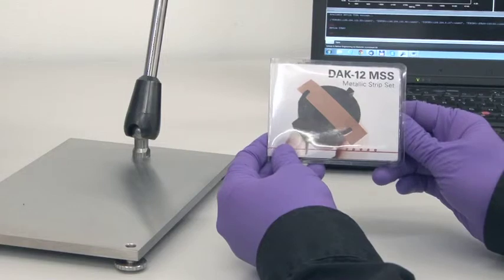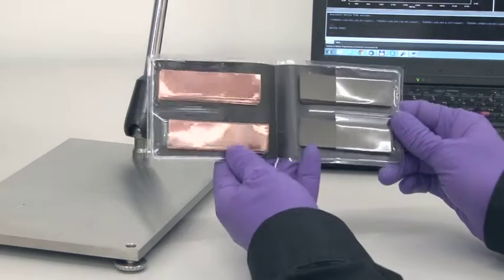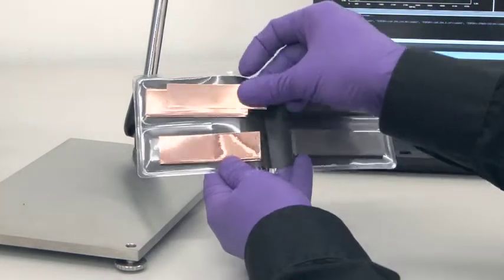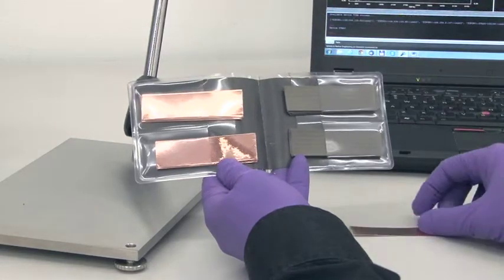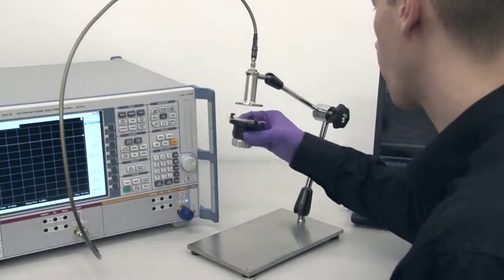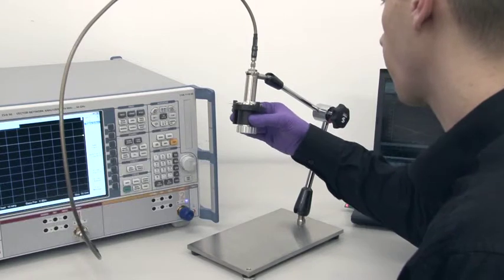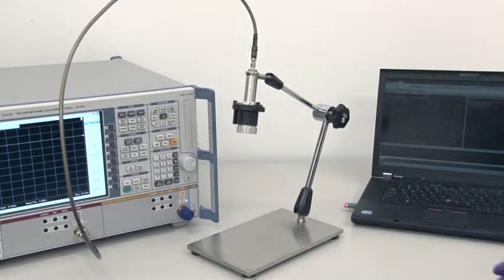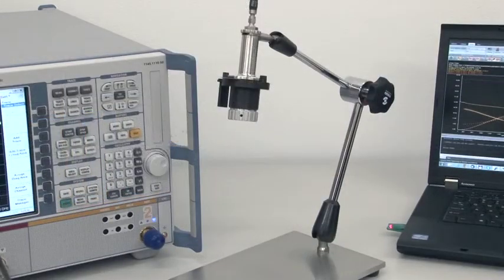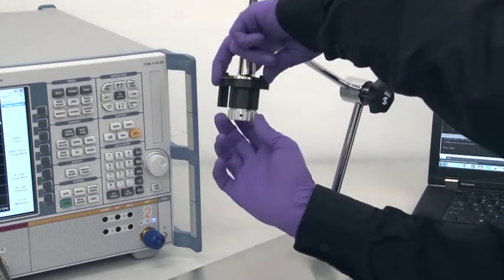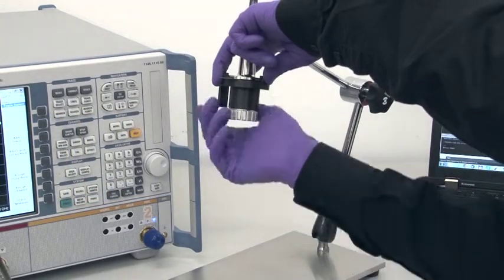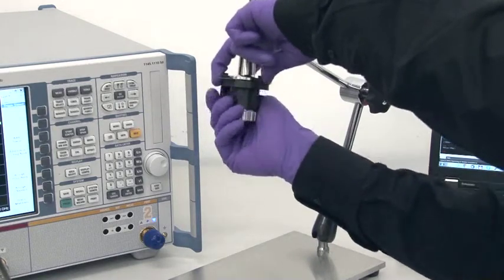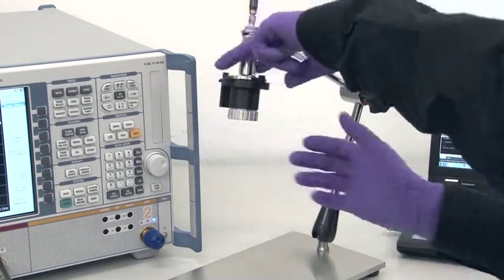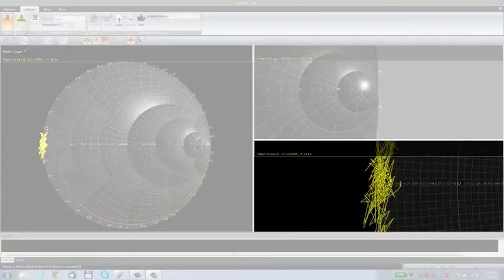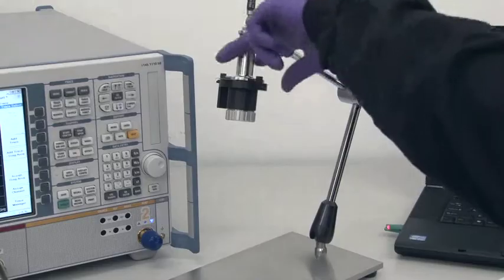High-quality measurement relies on precise calibration. Let us start with the short. Take a new metallic strip from the envelope. Mount the shorting block. Make sure the shorting block is in a secure position on the flange. By tightening the screw, make contact. Improve the contact by twisting the shorting block. Fully tighten the screw. Store it in the software.